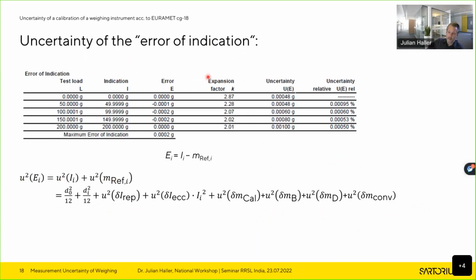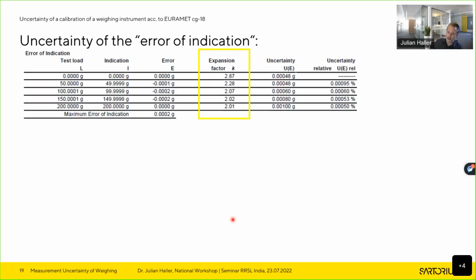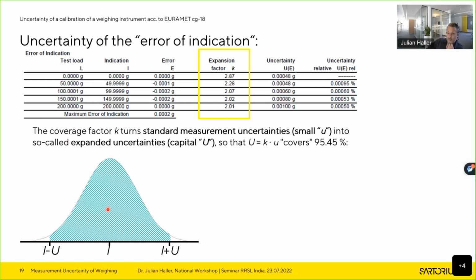One thing you also see here is the expansion factor. And just to explain that very briefly, for calculation of uncertainties, one usually uses the so-called standard uncertainty. And if you remember, maybe, hopefully, actually from your mathematics class in school, if you consider a normal distribution or a Gaussian distribution of uncertainties, then you might remember these Gaussian or normal distributions cover 68% probability if you go from the mean minus 1 standard deviation to plus 1 standard deviation. And a standard deviation is like a standard uncertainty. So that actually means if you state standard uncertainties, you will just have 68% probability that the true value is within this interval.